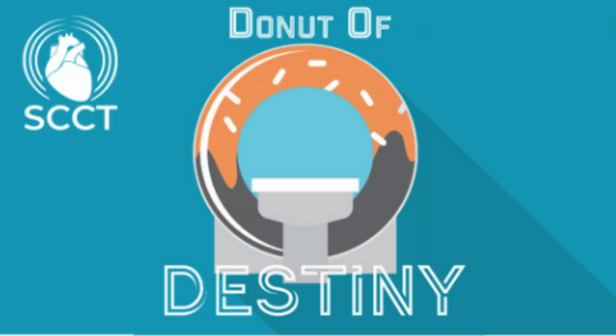Matthew, at the risk of sounding too reductive, this huge journey that the scientific community and obviously Siemens from the industry perspective have taken to achieve commercially available photon counting CT is really a change in the paradigm of the detector element. So to make sure I'm understanding, the historic, what you describe as energy integrating detectors, there's the scintillator intermediary. But with photon counting detectors, these do not have that type of intermediary. It's directly converting the X-ray photons into electrical energy. Is that correct? Completely right, Praveen.